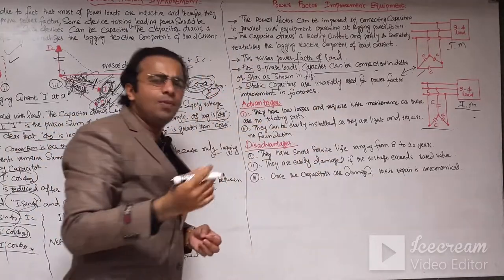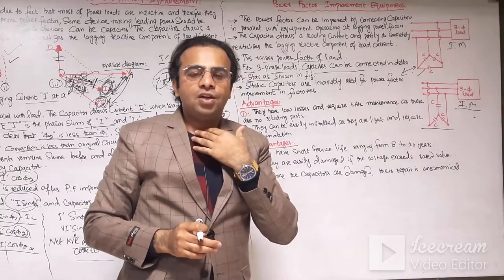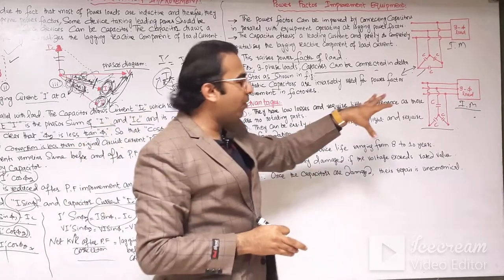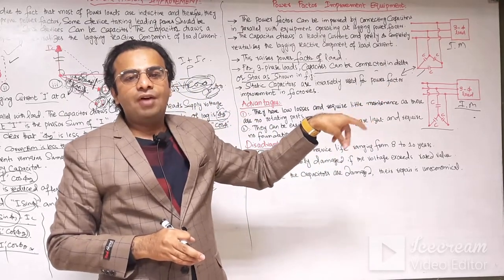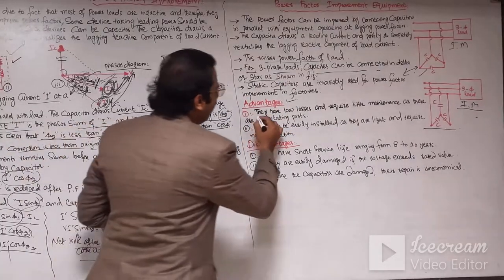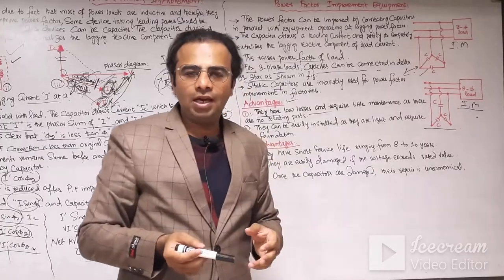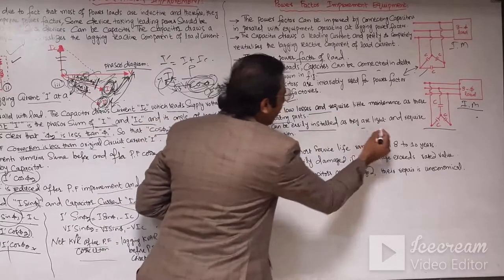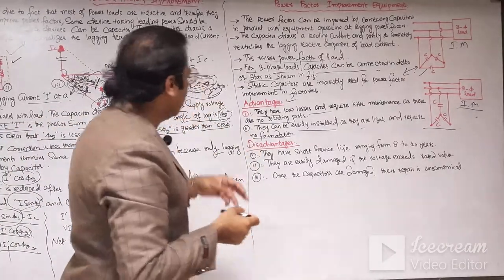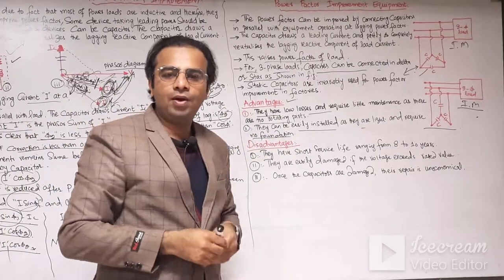Static capacitors are invariably used for power factor improvement of factories and industries. In factories we have three phase induction motors and heavy loads, so such capacitor banks are used for power factor improvement. The advantages of static capacitors are: they have low losses and require little maintenance as they have no rotating parts. They can be easily installed and are lightweight, requiring no foundation.